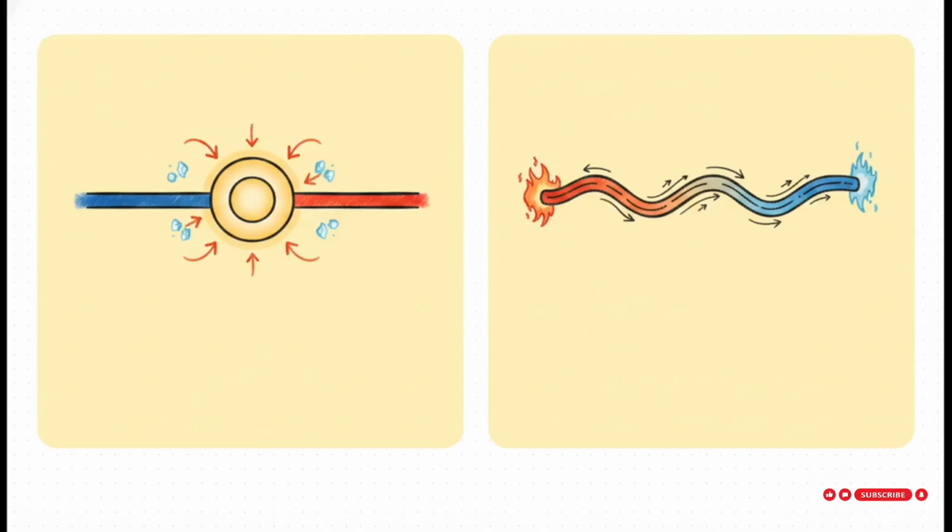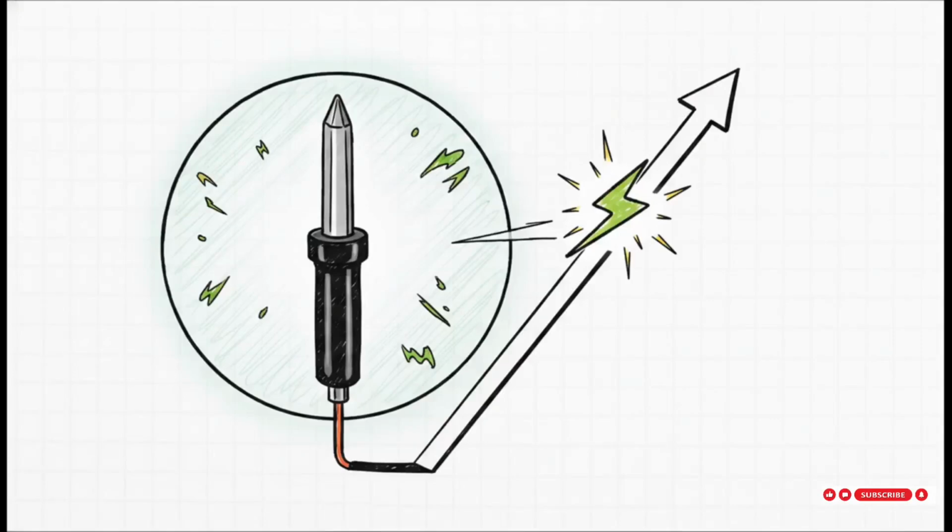Because we can carefully harness the Seebeck, Peltier, and Thomson effects, the thermocouple has become the rugged, highly reliable champion of industrial processing. By totally ditching those moving linkages, we eliminate dead zones entirely. We get an instrument with incredible precision of calibration, high resistance to extreme oxidation and corrosion, and a wonderfully linear relationship between the temperature and the millivolts it outputs. Usually that output is ranging from about 10 to 50 millivolts, which doesn't sound like a ton, but it is exactly what we need to get a perfect reading. It is a wonderfully elegant, pure physics solution to a really messy mechanical problem.